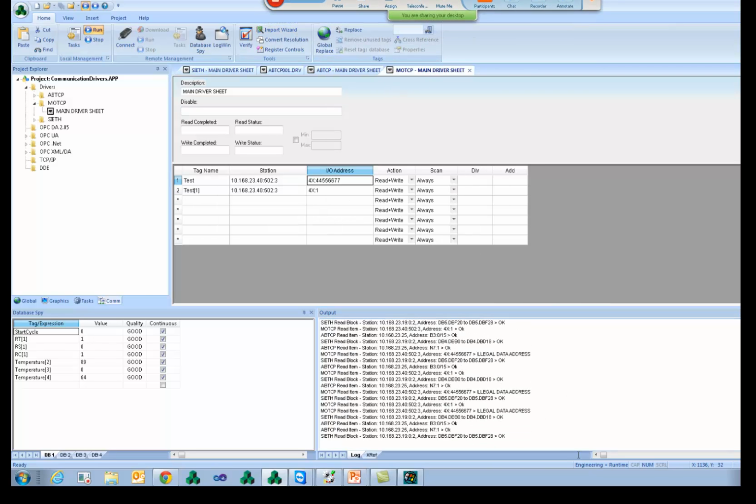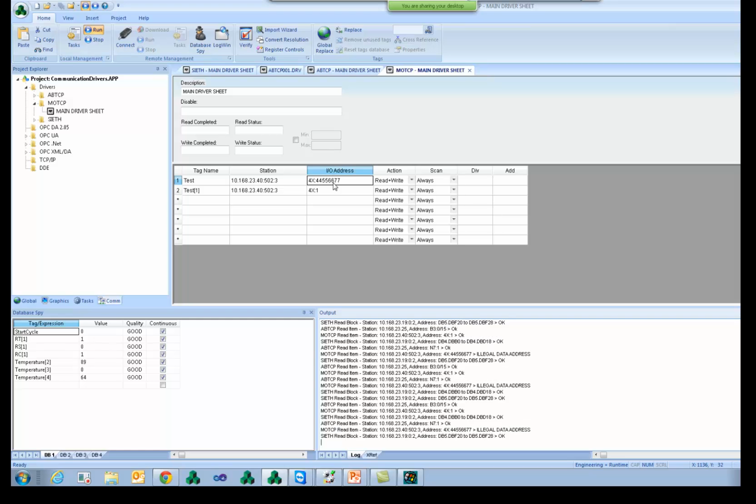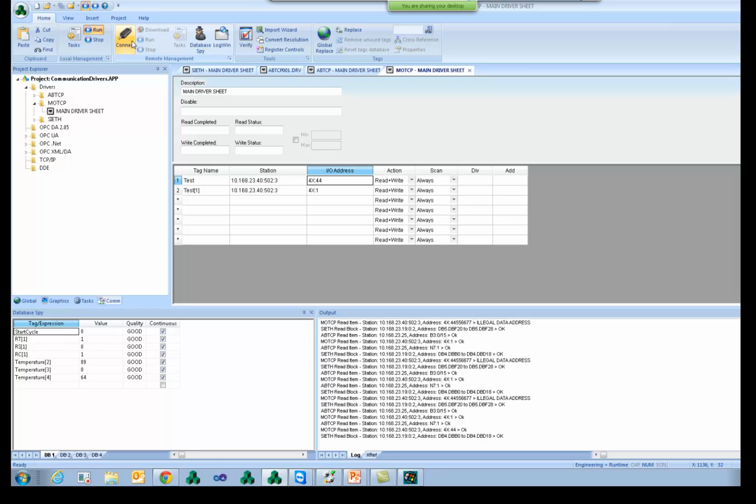On the Modbus, we see the error happening here. Oh no, I mistyped that. I don't need to talk to all that. I'm gonna talk to the 4x44. I change that, I save, and look, all my communication is okay now.